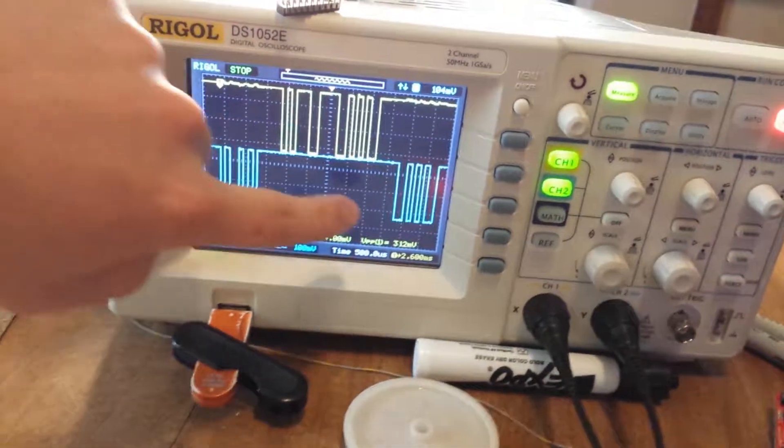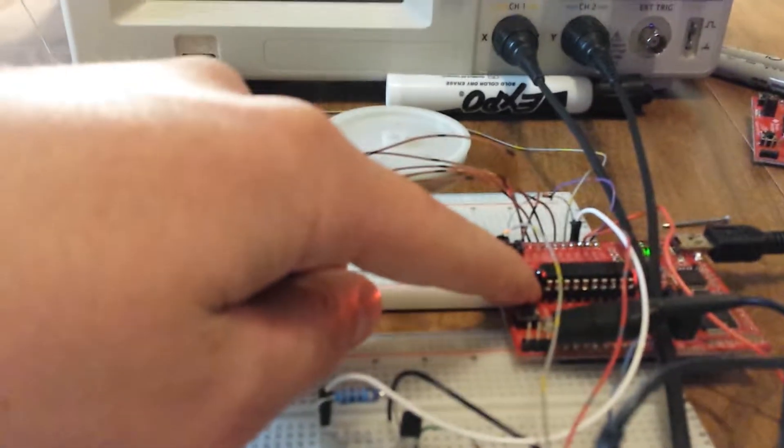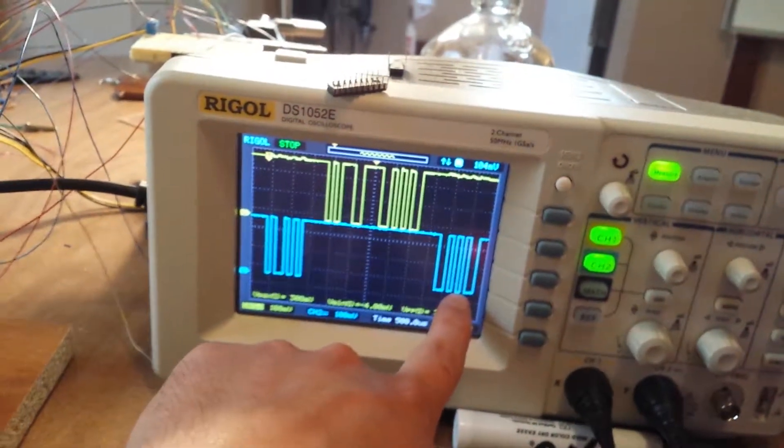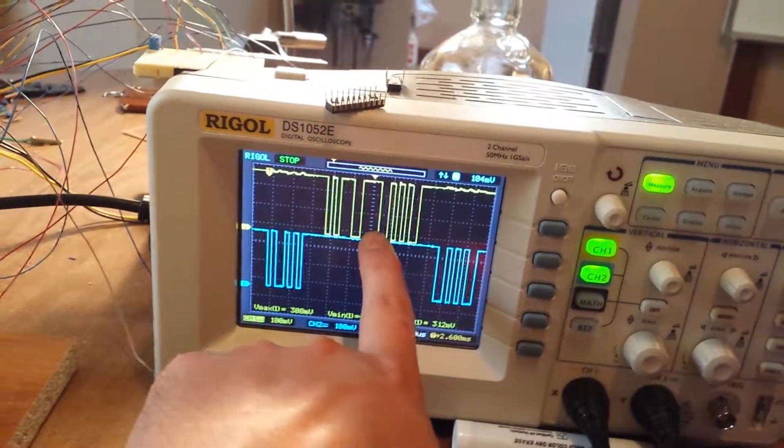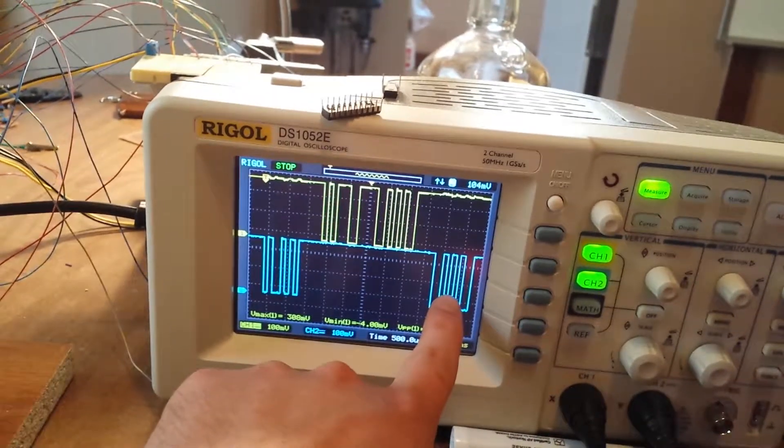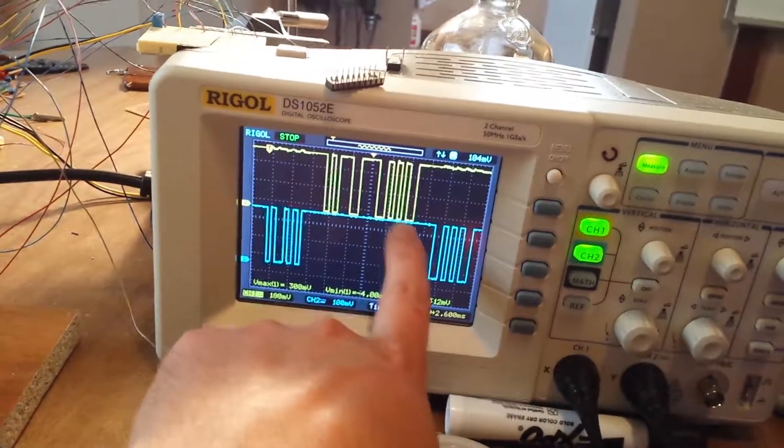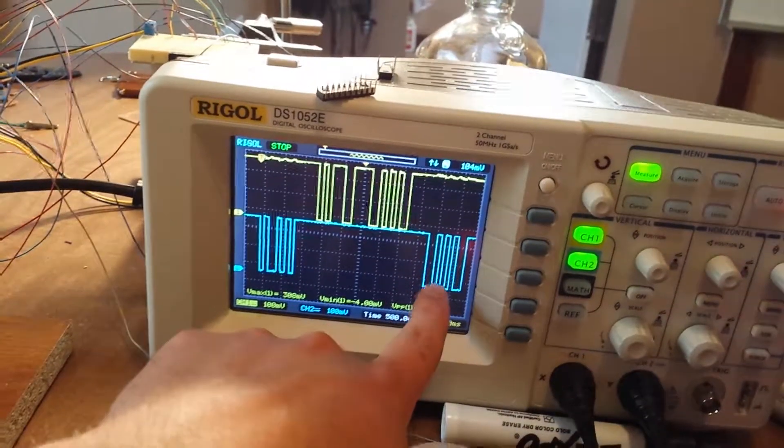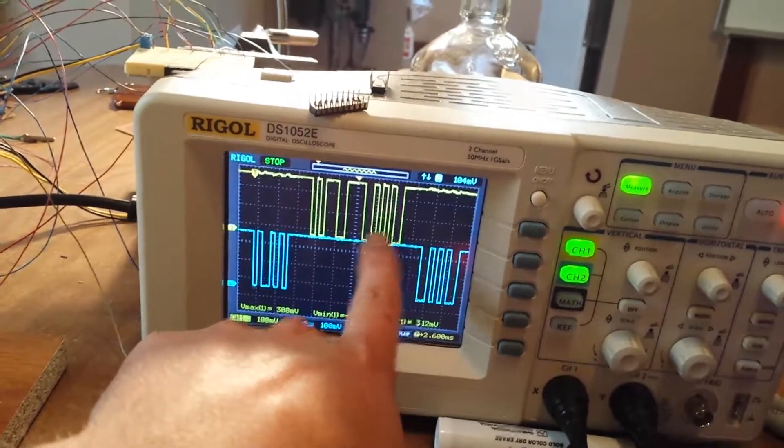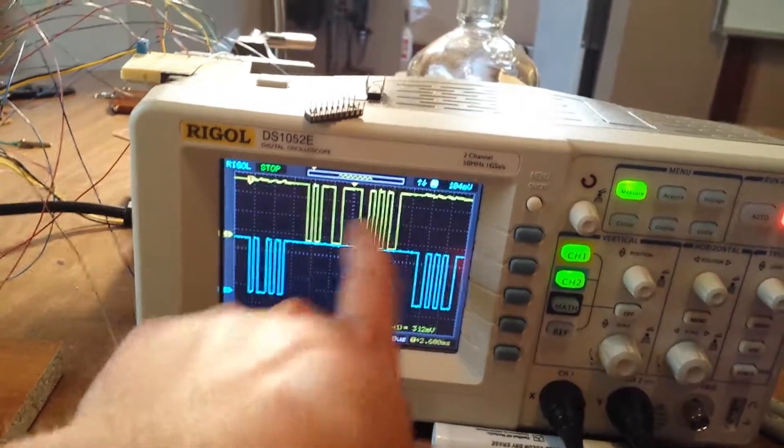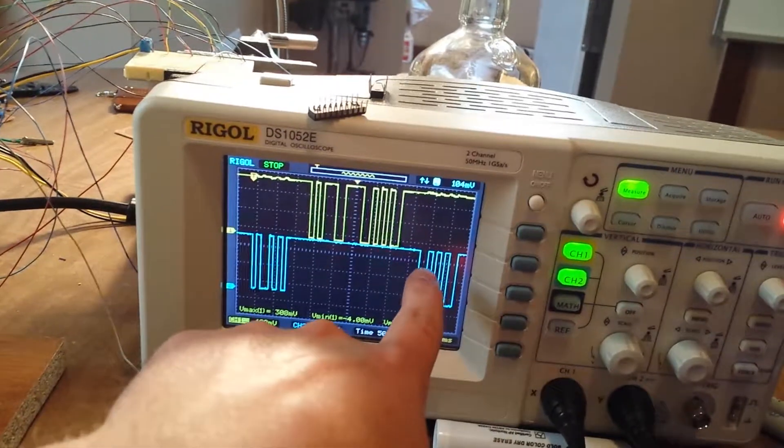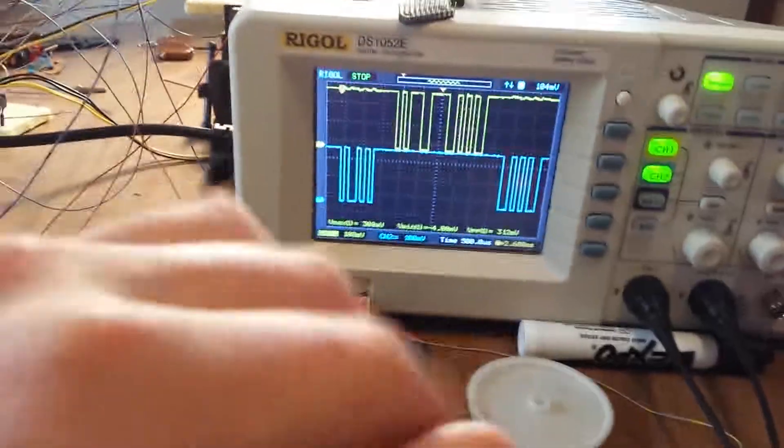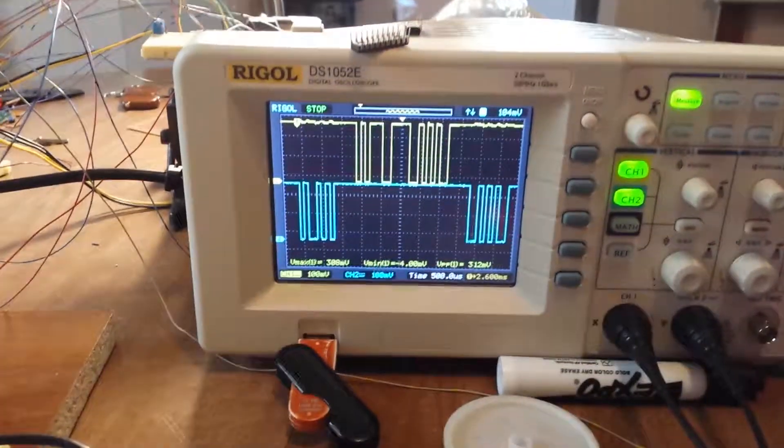And here's what I actually said. If this doesn't match this, then there's a serious problem and we need to resend the information. So, what it does is, it, if this information was incorrect, it would send this whole information again. And this, and then the, it would resend this until it got it right. And once it has it right, then it's able to do other code. So, really, this is like a handshake between the two controllers, making sure the information is correct and there's no errors in the transmission.